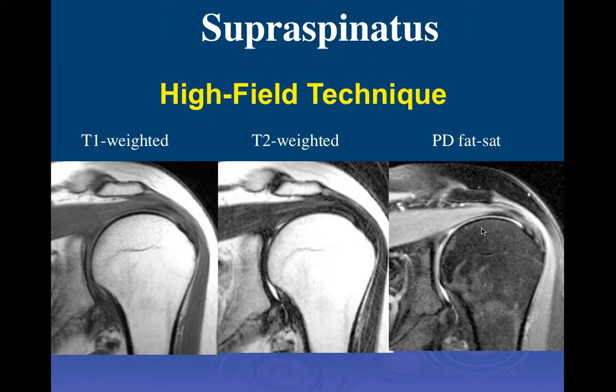I like a TE somewhere around 30 to 34 milliseconds at 1.5 Tesla, a little bit less at 3 Tesla. The T2 times of tissues are slightly different at different field strengths — T2 times become less at 3T. Therefore you can shorten the TE a little bit at 3T, which maintains the same contrast but actually gives further improvement in signal-to-noise because you have less decay time. There are several ways you can win going to 3T.